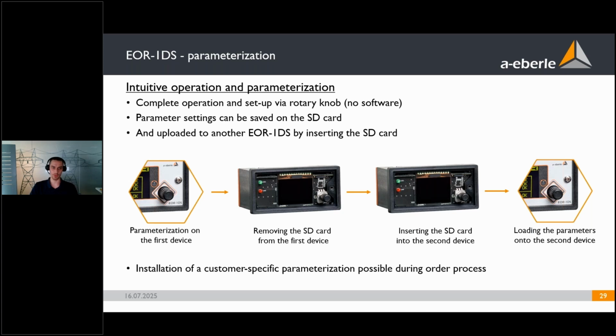The complete setup is done using the rotary knob on the front of the device, so you do not need parameterization software. And after parameterizing one of the devices, you save the parameter set on your SD card, then remove the front panel, eject the SD card, insert it into another device, and then simply load the parameters from the SD card and maybe only adjust sensor factors or adjust nothing at all, depending on the situation, of course. So really easy parameterization and installation, and firmware update is done the same. It's also possible that we do the parameterization for you, either on site or we do it here, and then you get the devices with a customer-specific parameterization already on your device when it arrives.